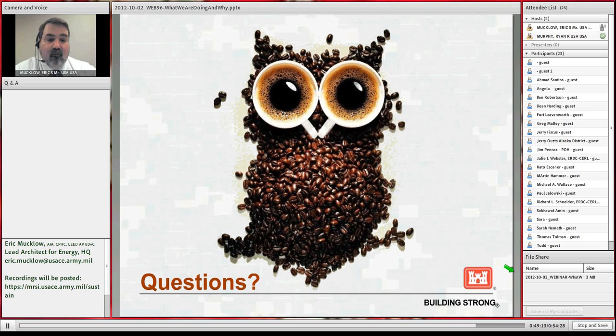The performance metrics for a major renovation, I've seen in some things where they reduce the levels required, or they acknowledge that they'll end up with a higher energy intensity per square foot. There's only so much you can do. You'll have to look at the thresholds for the total facility, and if you have a project under $700,000, how big is that in proportion to the entire facility? To see if that qualifies as really, are you doing a major renovation from the 109.1 perspective versus something minor, to see if that applies to you or not.